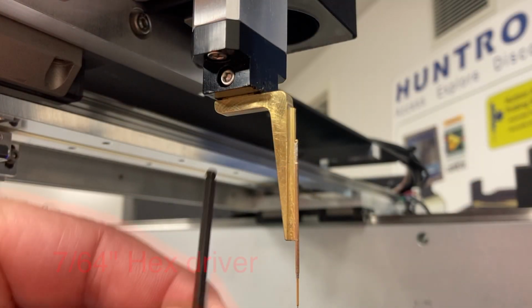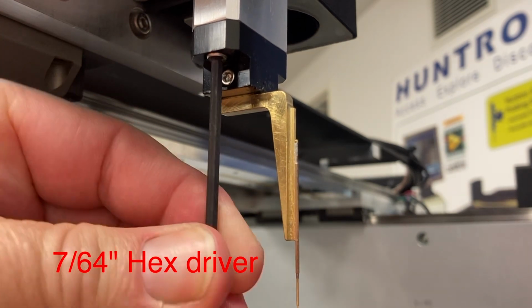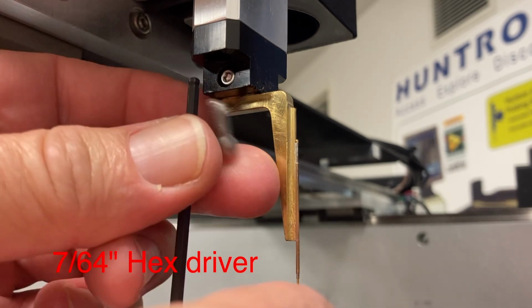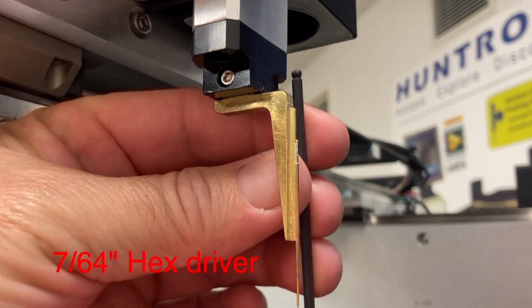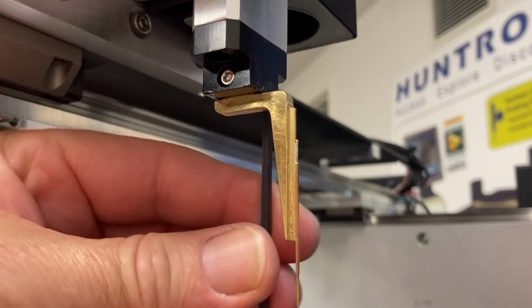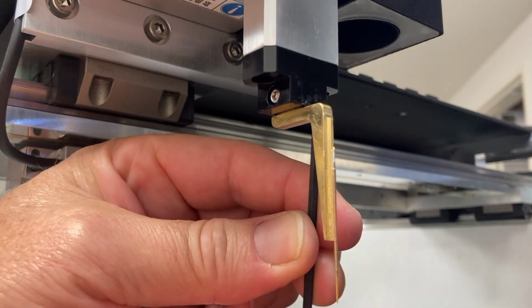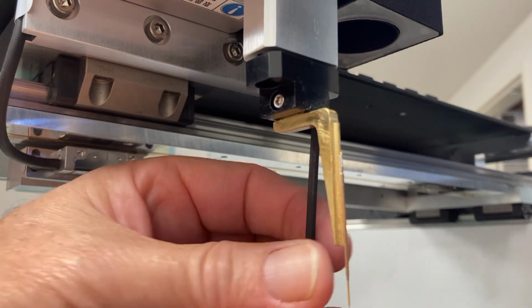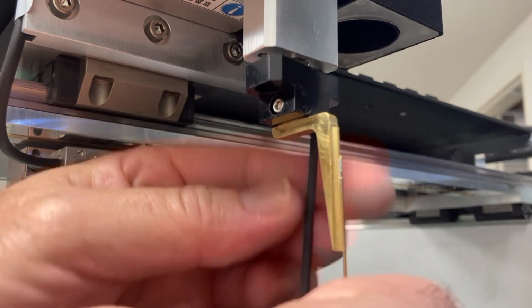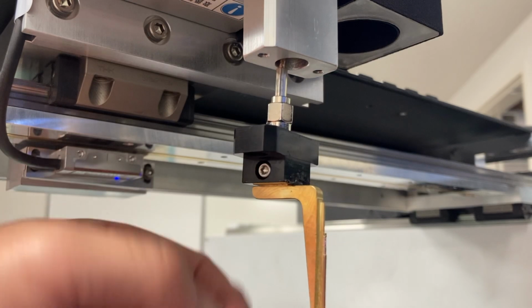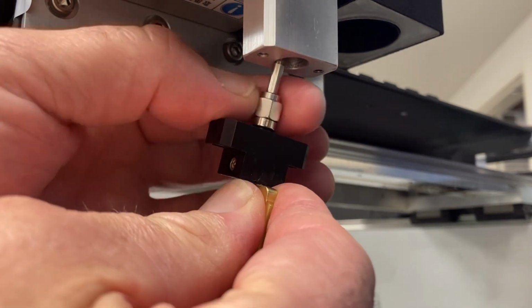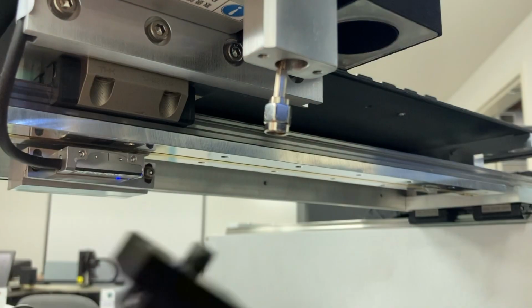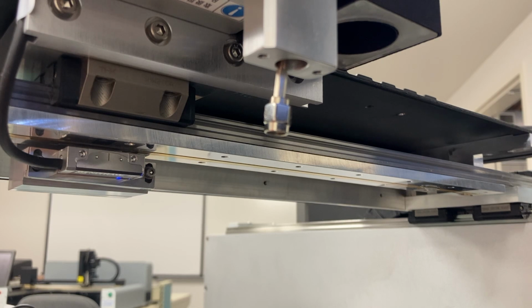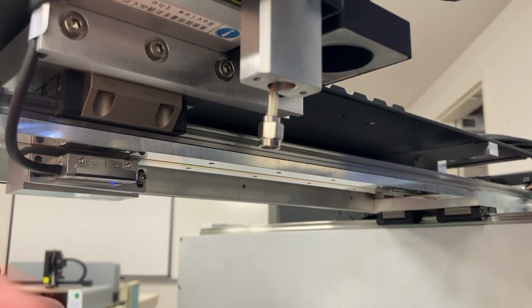To remove and replace the probe holder, there are two screws that attach it to the Z-axis shaft of the prober. Remove the front screw, and then remove the rear screw. Once the screws are removed, gently pull down on the probe holder to expose the SMA connector. Unscrew the SMA connector, and then you've removed the probe holder. To install the new probe holder, simply reverse the steps.